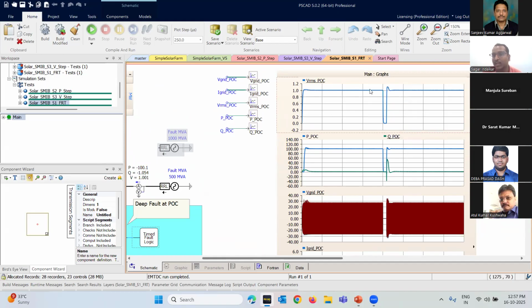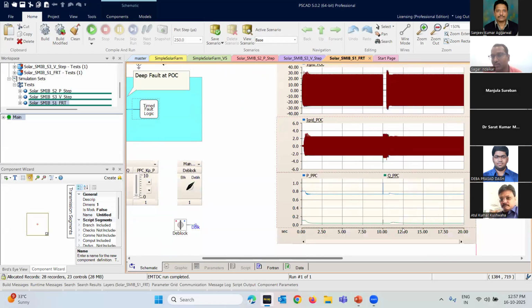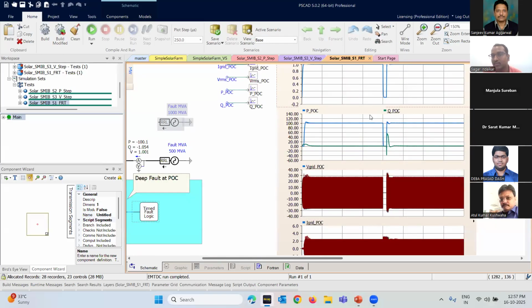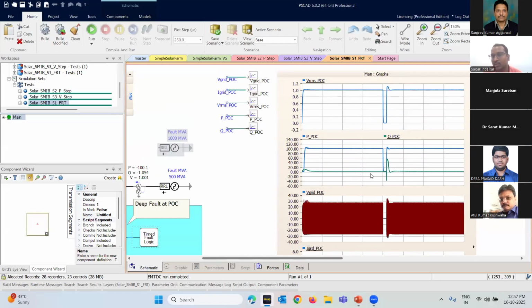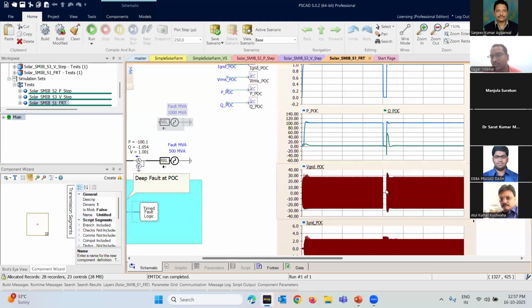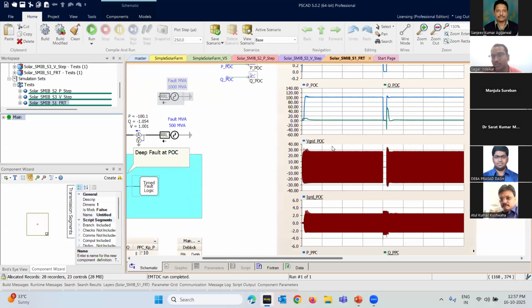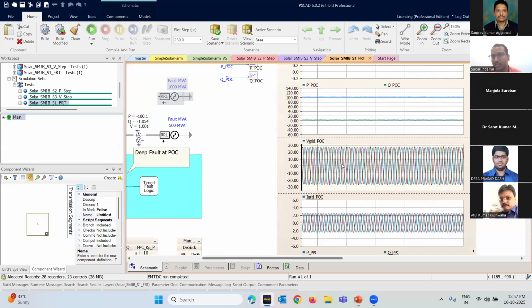So VRMS at the POI reduced to almost zero at t equal to 10 seconds. And so my active power reduced, and my reactive power is also reduced to zero. The voltage fell to a very low value here. See, this is the instantaneous voltage.